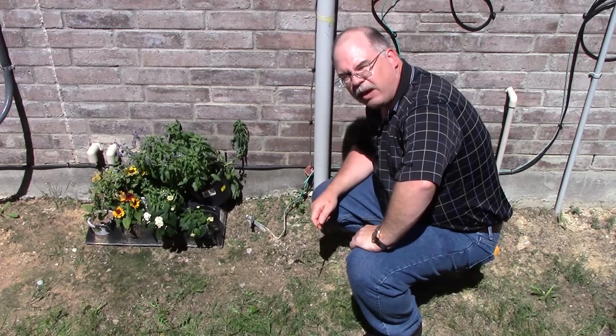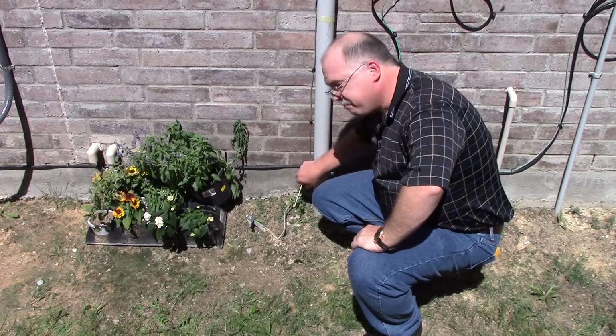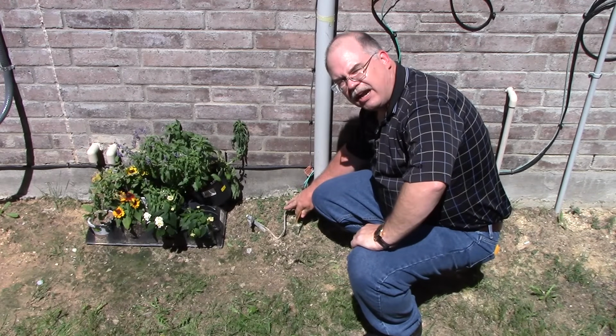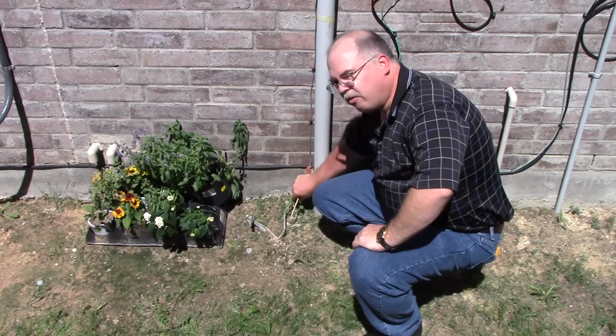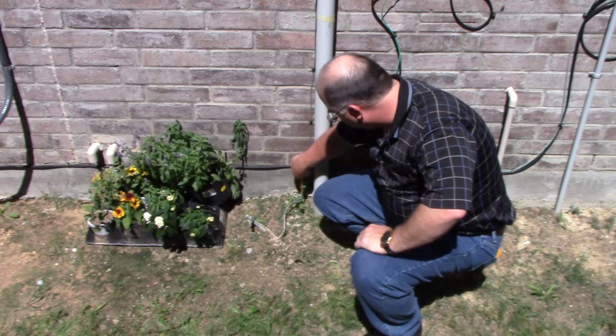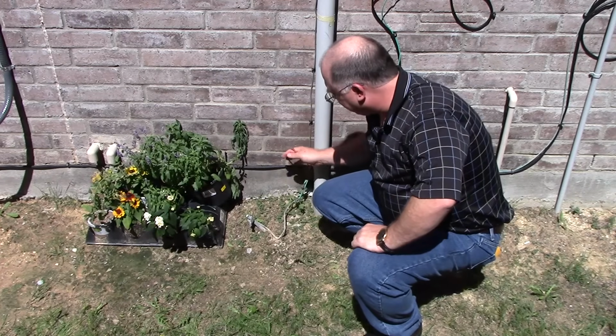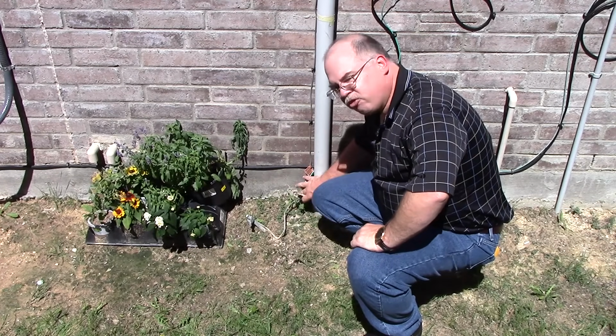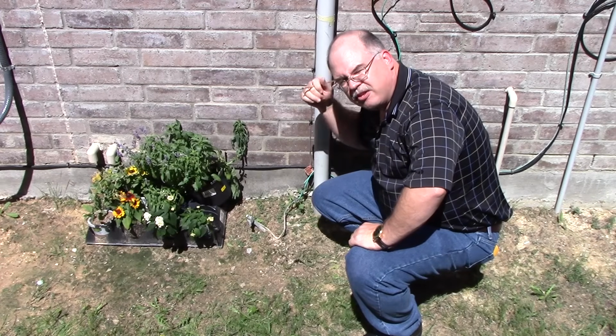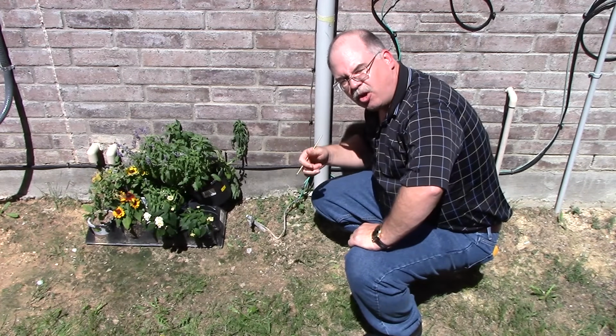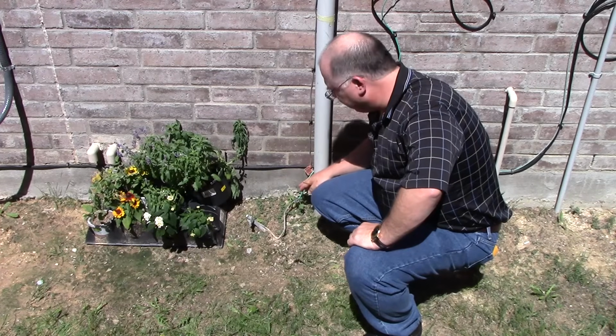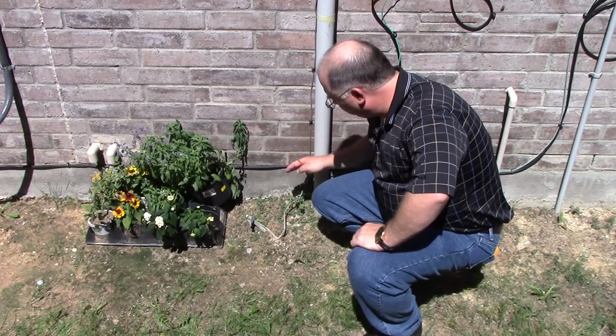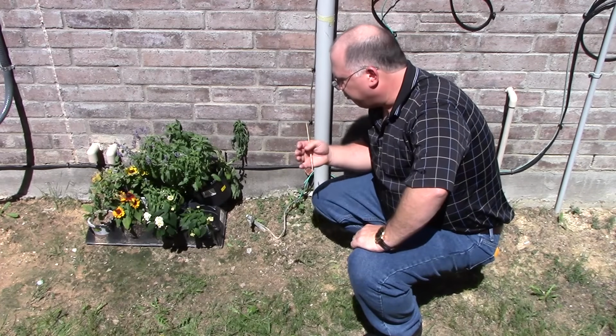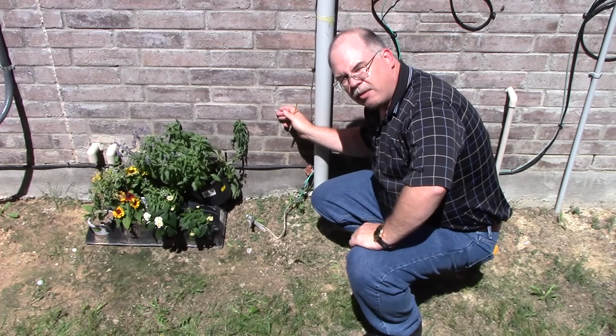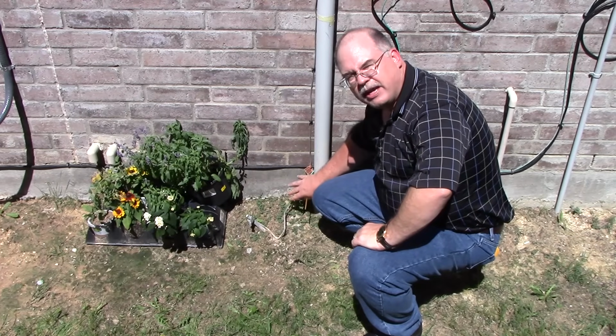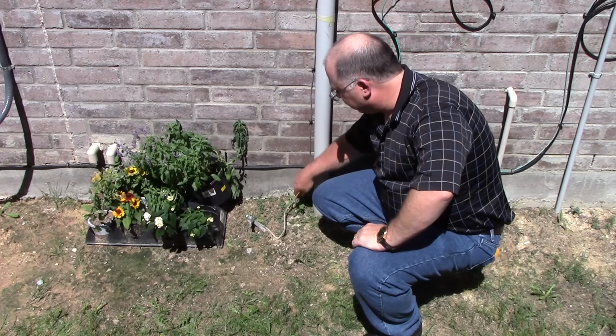Now, this was actually done before that was in the National Electrical Code, so they actually did make these connections, but they made them directly to the grounding electrode conductor. And if you're a home inspector, this is okay. I would accept this. Just check and make sure they're nice and tight and everything looks good, and that's fine. So that's the part that I want to just emphasize. These are going to go up to the TV cable system, to the data cable, the telephone, all those communication systems and satellite dishes. They're required to make their connections, and so you have to provide them a place to do that. Prior to that intersystem bonding terminal requirement, what you had to do was bring it over to the grounding electrode conductor, and that's what they did here. So this is all acceptable.